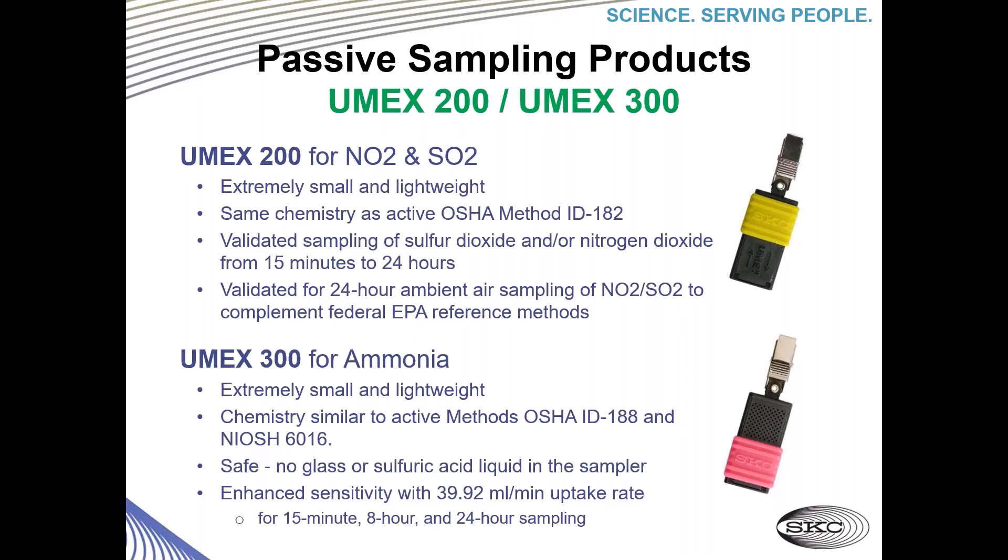Ammonia can be a challenge to work with, and our Umex 300 can take care of that. Same design, with chemistry similar to the active method OSHA ID-188 and the NIOSH 6016 method. One convenience is that it's safe because it doesn't have any glass or sulfuric acid liquid in the sampler as with other methods. It also has enhanced sensitivity with a 39.92 milliliters per minute uptake rate for 15-minute, 8-hour, and 24-hour sampling.